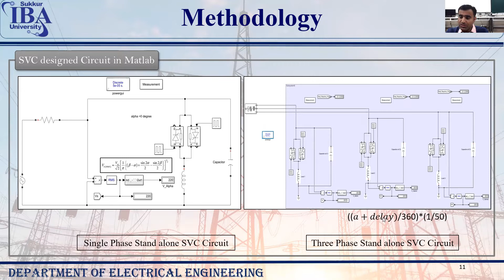And this is the output of the previous circuit. Basically, we use a 10 megawatt capacitor and a 12 megawatt inductor. Initially, when 100% inductor is in the system, only 2 megawatt is at the output. 10 megawatt is compensated by this capacitor. By regulating the value of the firing angle, the output of the system varies.